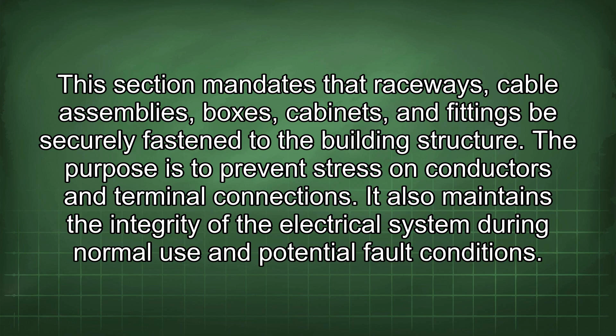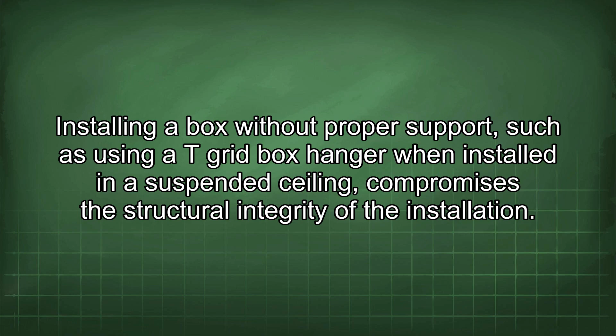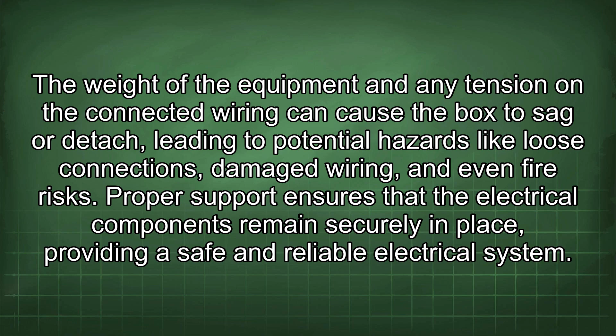Installing a box without proper support, such as using a T-grid box hanger when installed in a suspended ceiling, compromises the structural integrity of the installation. The weight of the equipment and any tension on the connected wiring can cause the box to sag or detach, leading to potential hazards like loose connections, damaged wiring, and even fire risks. Proper support ensures that the electrical components remain securely in place, providing a safe and reliable electrical system.